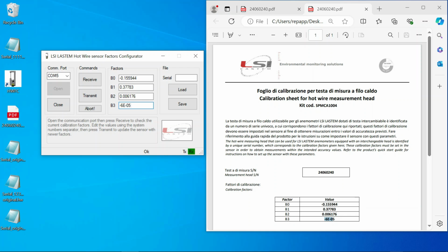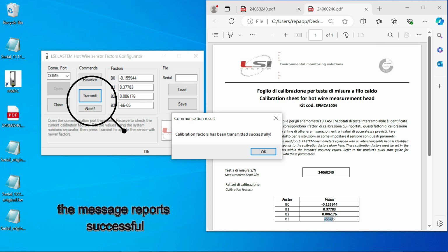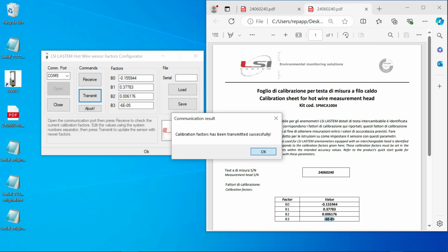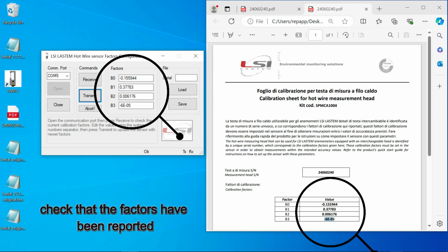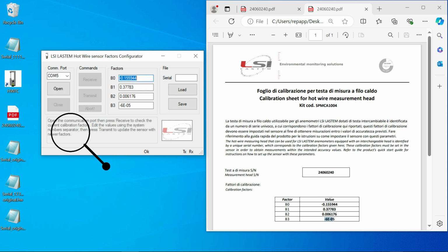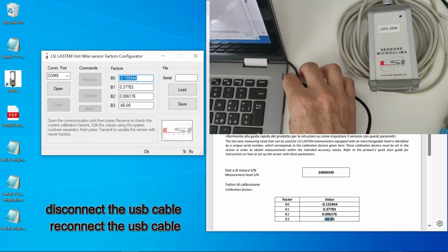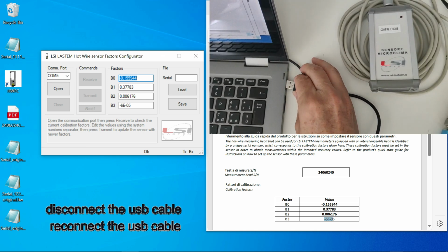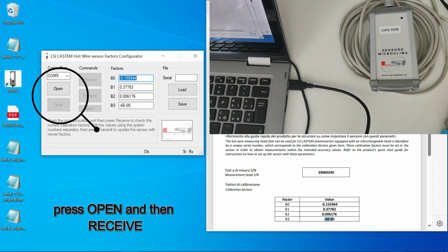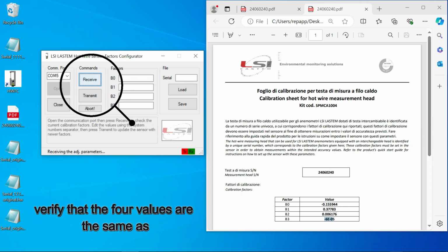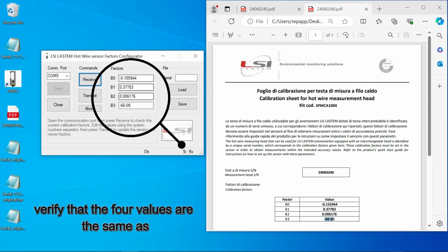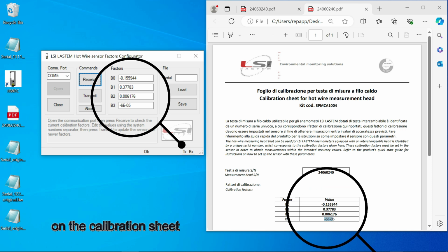When finished, press Transmit. The message reports successful transmission. Check that the factors have been reported correctly. To do that, press Close, disconnect the USB cable, reconnect the USB cable, press Open and then Receive. Verify that the 4 values are the same as on the calibration sheet.